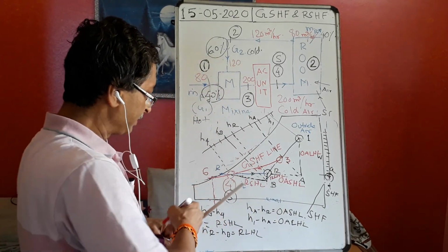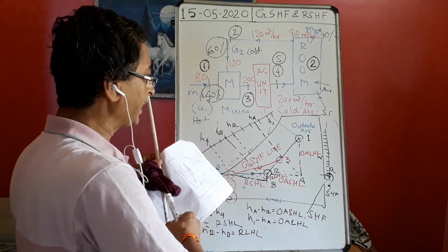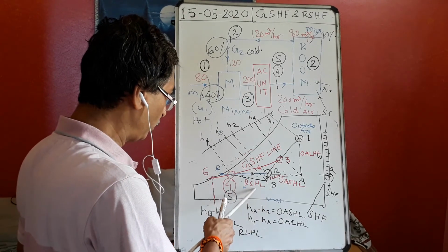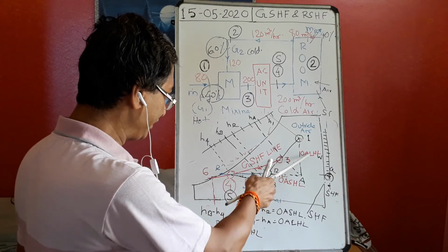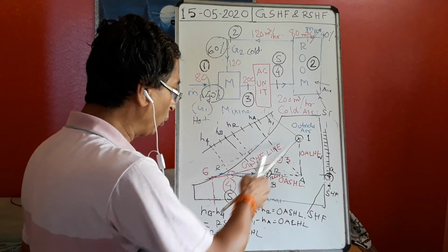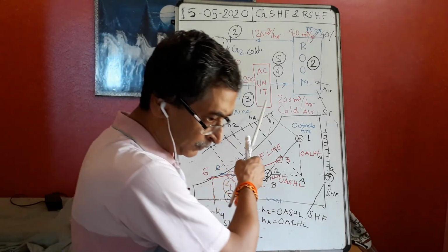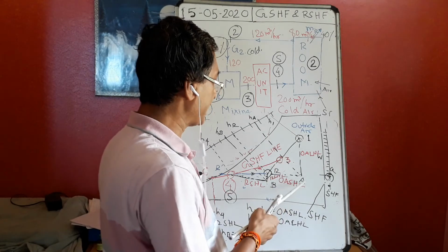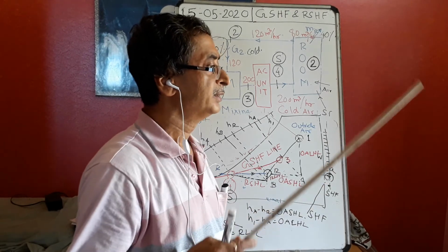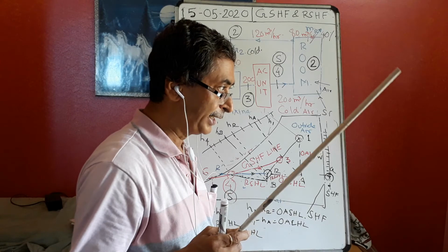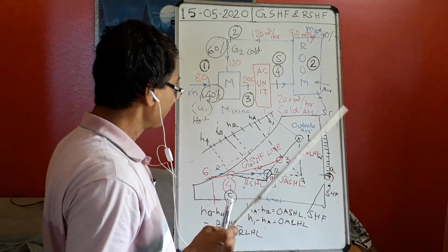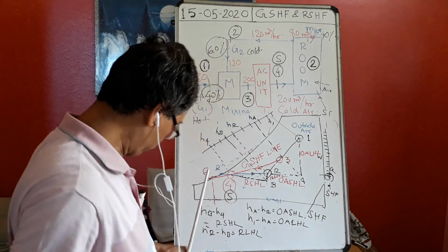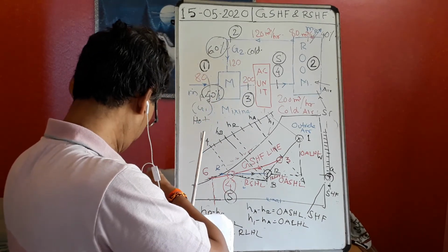Now I can find out the total load: outside air sensible heat load plus room sensible heat load plus outside air latent heat load plus room latent heat load. If I know all the loads, it will be easy for me to design the AC unit, isn't it? For the moisture, I have to find out how much has to be removed, so I have to install a dehumidifier. Now there is another line I have not told about, so this line has to be explained now.